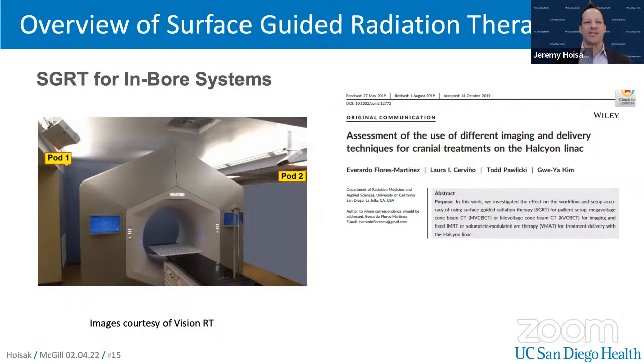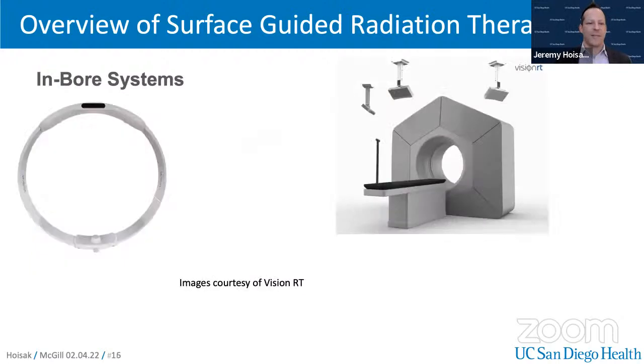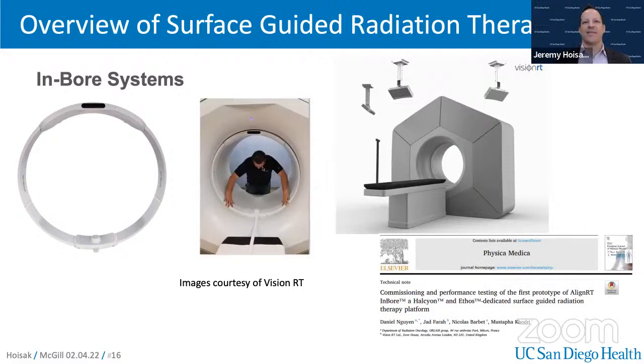AlignRT came up with a solution to address this problem by placing a SGRT camera within the bore itself. And I'll show you that right here. So this is what they call the AlignRT in-bore. It's actually a plastic insert. It doesn't actually change the linac in any way. It just snaps in place and it gets external power. They claim that an engineer can do this in just a couple of hours. It doesn't require you to open up the gantry at all. So it is an interesting solution.